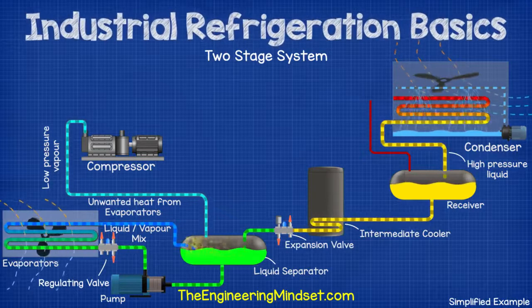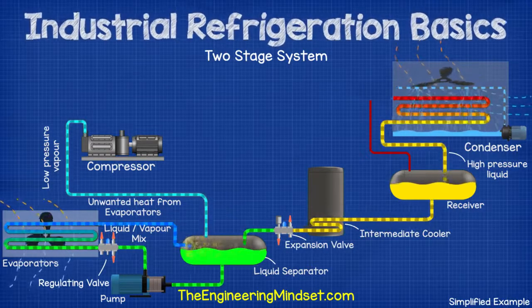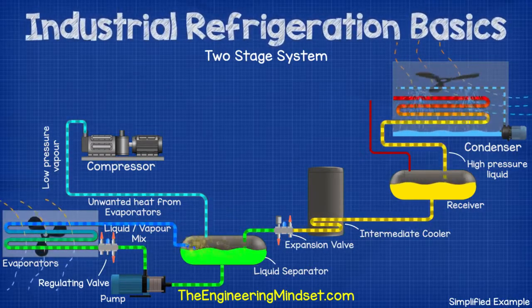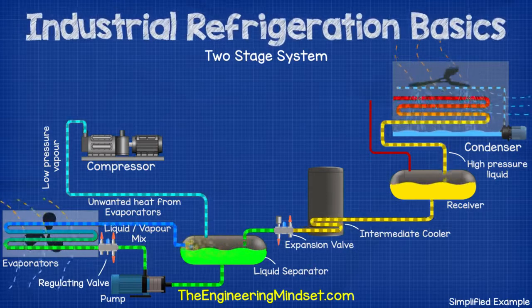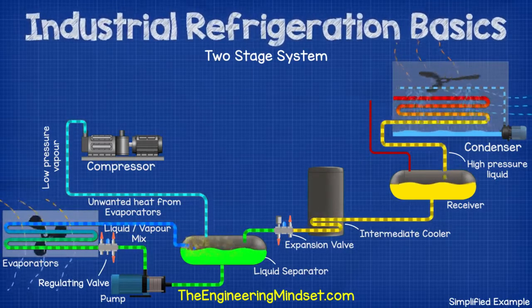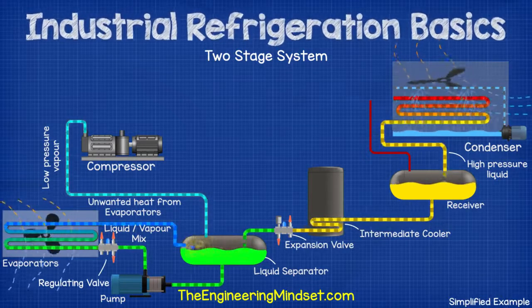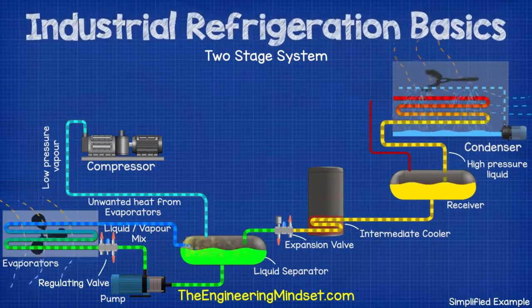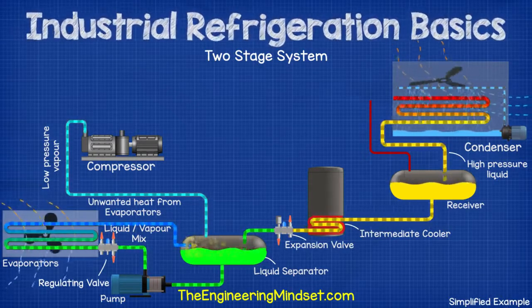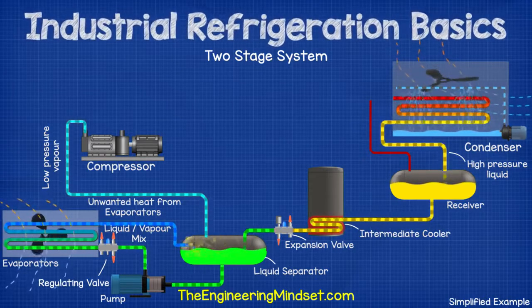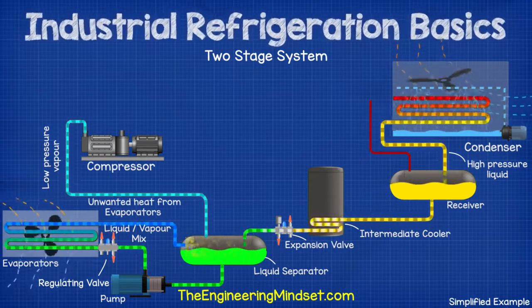We again have the refrigerant flowing the same cycle, but we have a few other components and cycles. In this type, we have a tank called the intermediate cooler, which sits between the receiver and the expansion valve. The main flow of refrigerant passes through the coil inside the tank, and then into the main expansion valve, just like the single stage system.